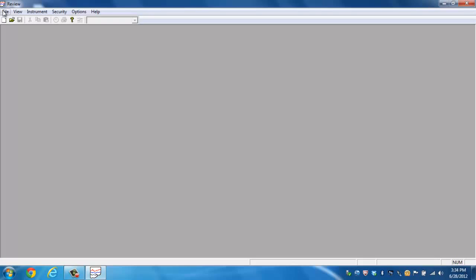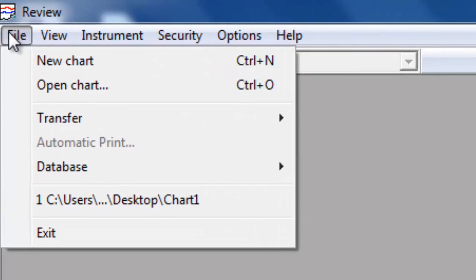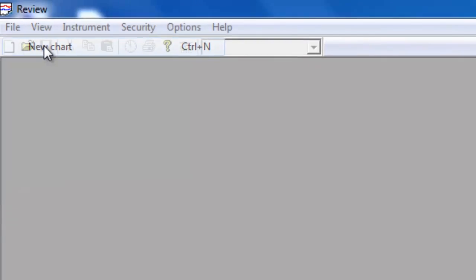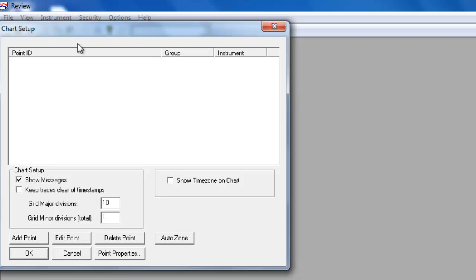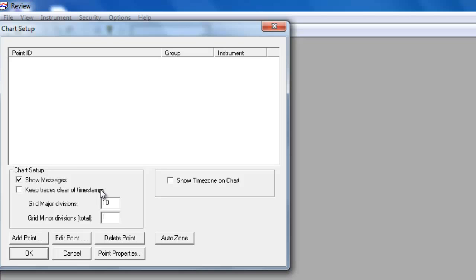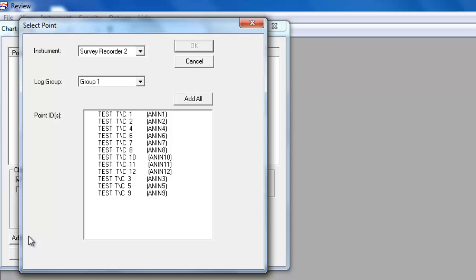This is a simple process. If you click on file and then go to new chart, it pulls up a chart setup window. Now what you see in front of you right now, the only thing I want to mention is underneath the chart setup there's a show messages. You can optionally turn this off if you want, but when you have show messages, this shows information pertaining to any batch information you may have, a specific user logging in or out, a configuration change, or even some type of system alarm. So I'd recommend leaving it on. Just a reminder, once you create the chart, you can always turn the messages back off at a later point. Now in order for us to recreate this chart, we actually need to add points to it.